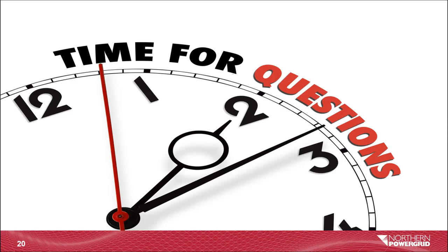Question from Josh. How can I use the LTDS to find the capacity at substations? What information do I need to pay particular attention to? Hello, Josh. If you download the LTDS for either license area, Appendix 5, Table 3, load information details the maximum demand, the forecast maximum demand for the next 5 years, the minimum demand for last year, and also the firm capacity of each of our primary substations and supply points.